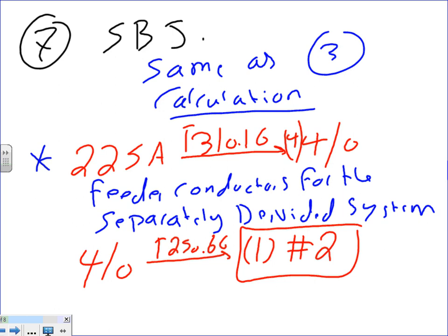First you size the feeders and then you size based on the feeders. Did we say that in the number 7? Size based on the feeders. So number 7 says 250.66. If larger than 1100 kcm, take total of the feeder. Yeah, the same you're going to apply if larger than 1100 kcm. And we know that the secondary amps will be more than the primary. Yes. So yes, good.